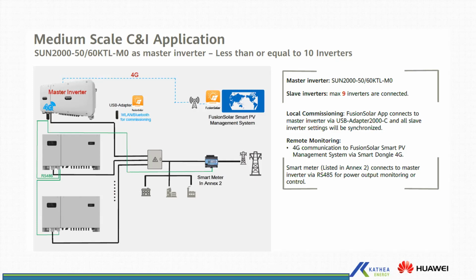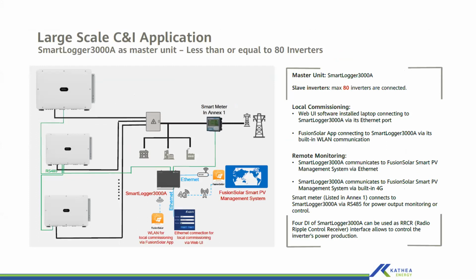So when you are using a smart dongle, your slaves are limited to 9. Right, the smart dongle can only support 10 devices. So, master being 1, you can only have 9 slave devices. And then if your inverters are more than 10, you definitely need to use a smart logger, which supports up to 80 devices, so you can connect up to 80 inverters on it. The smart logger comes with 3 built-in COM ports. Per COM port, the number of devices that you can connect in a daisy chain is 30. So for each COM port, you can only daisy chain 30 inverters.